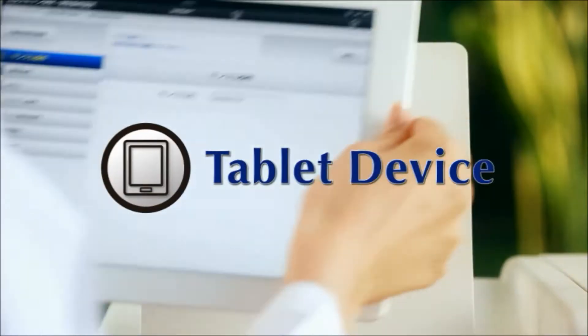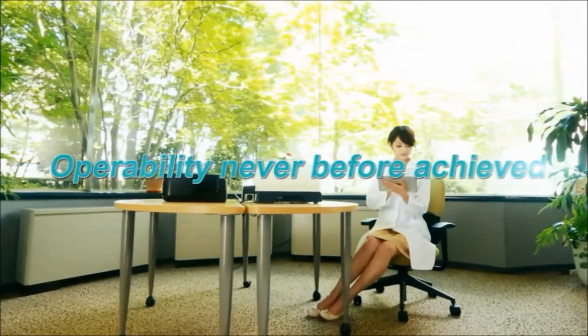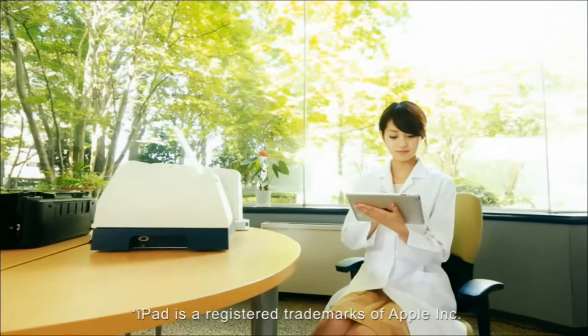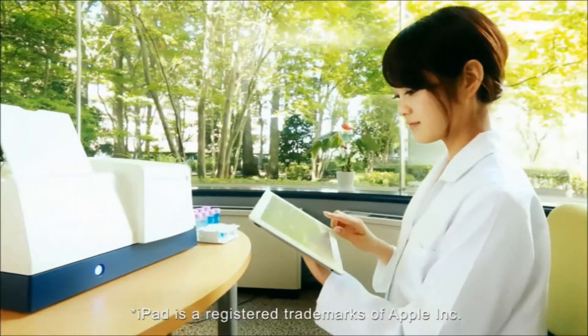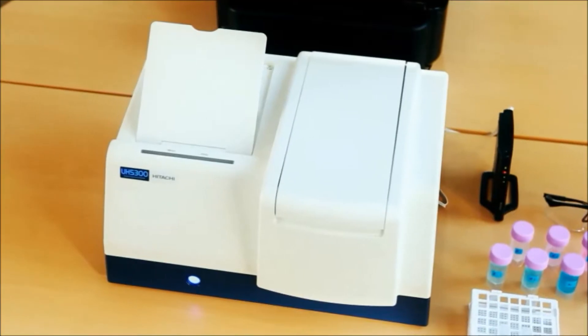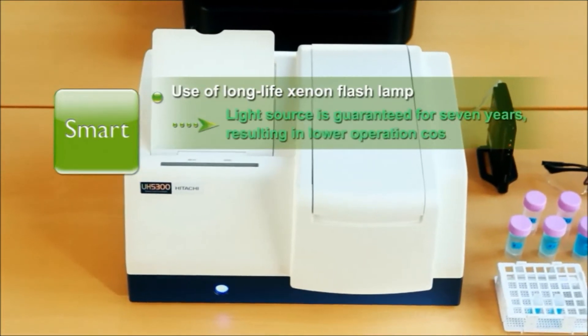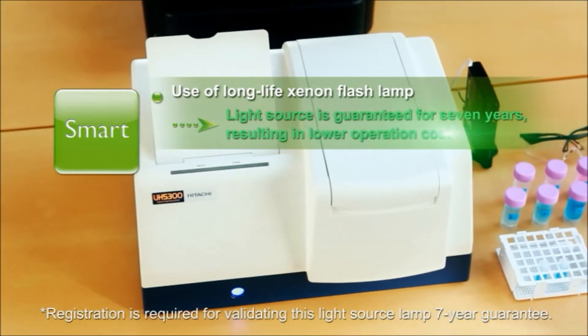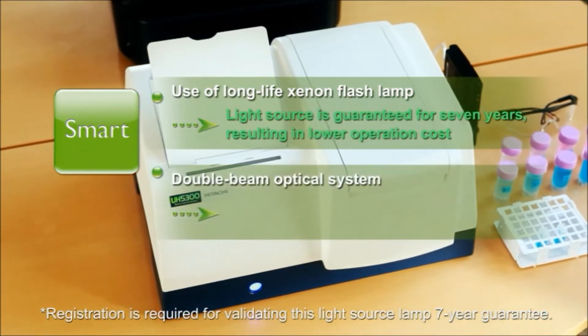With a tablet device, a new user interface is born. Therefore, spectrophotometers have made further progress. The most advanced spectrophotometers are obtainable only from Hitachi, due to adoption of a xenon flash lamp — a long-life light source. A light source life of seven years is guaranteed, meaning the burden of maintenance work is reduced for the user.